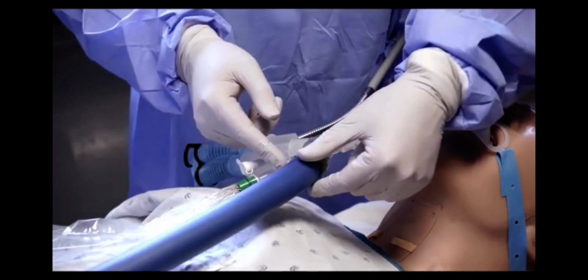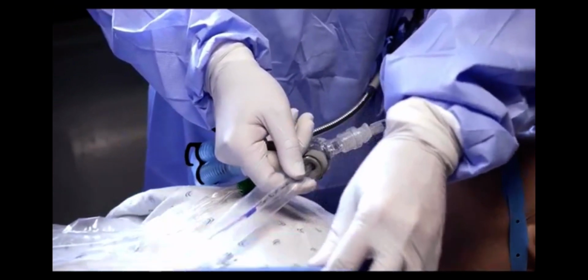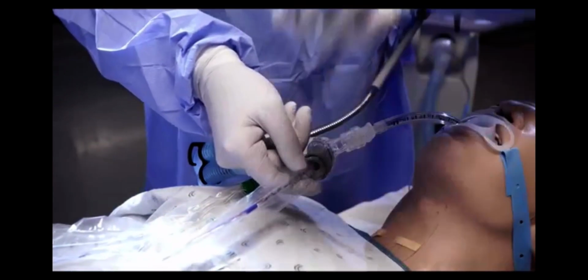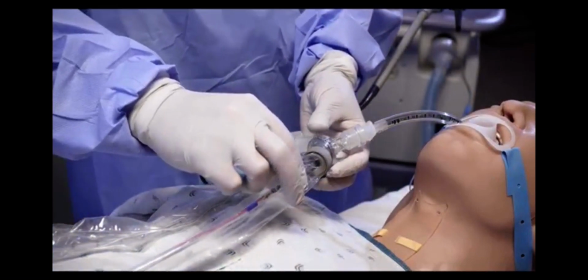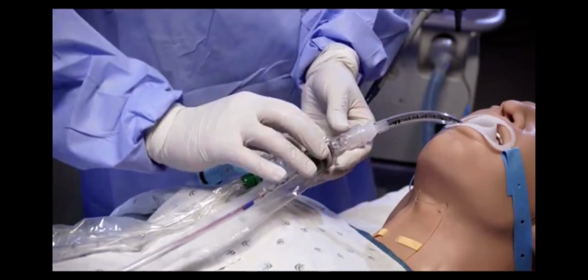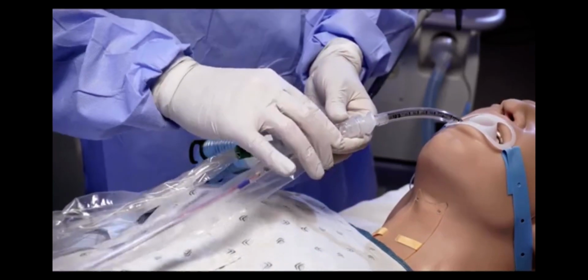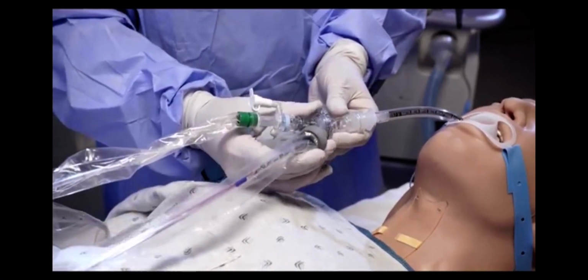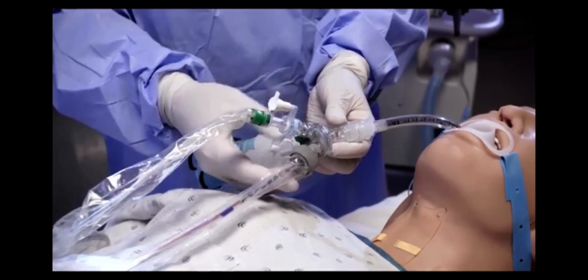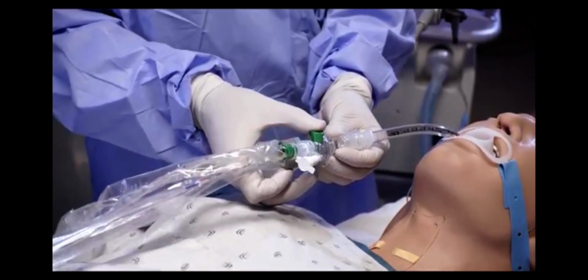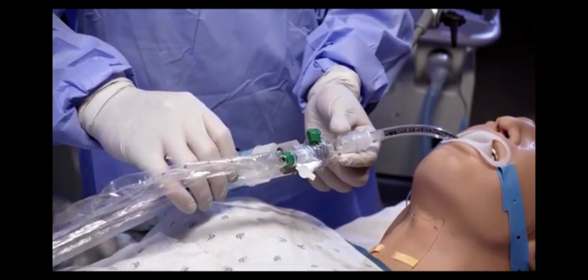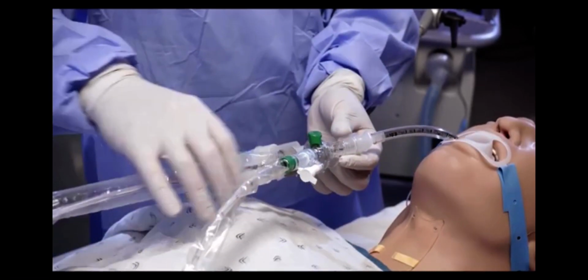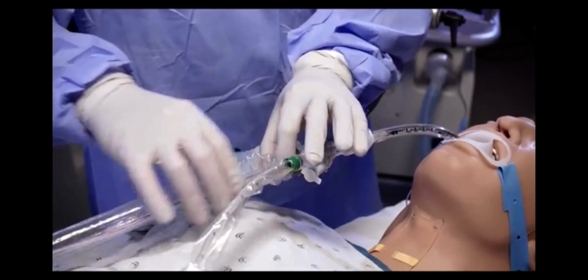What you can see here is the setup where the device is already attached to the multi-port catheter, and before using it, the foam protector is removed. In order to engage the device, now we have already sampled with the suction catheter, so we no longer need the suction catheter. The device is swiveled in order to engage the UV light catheter. The catheter is inserted all the way until the tip is sitting at the tip of the ET tube.